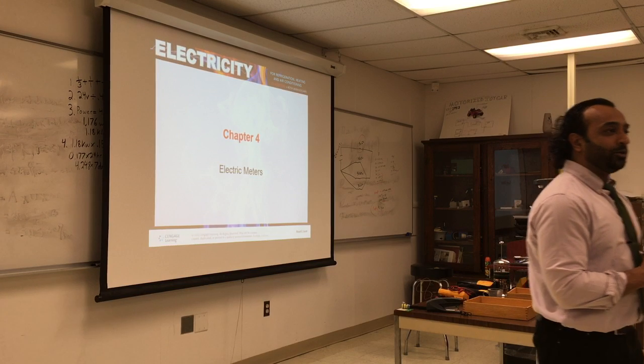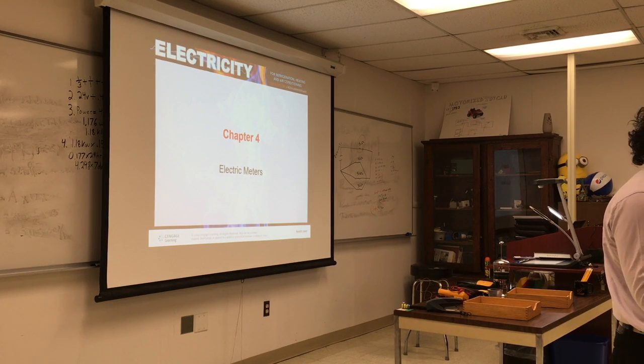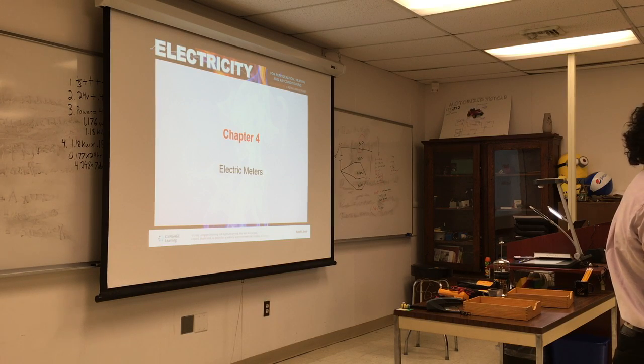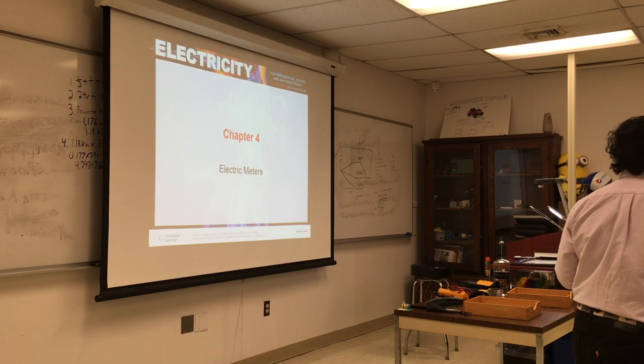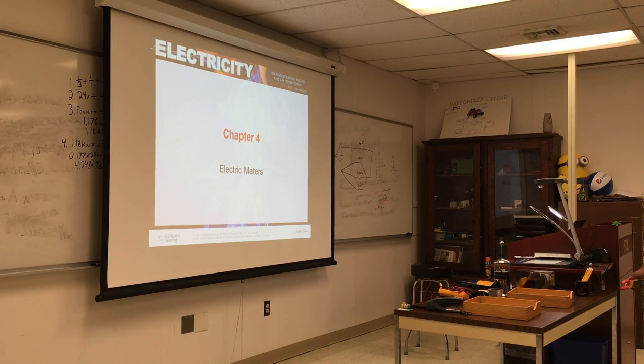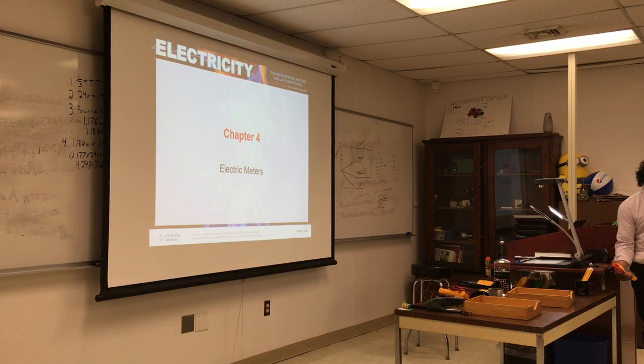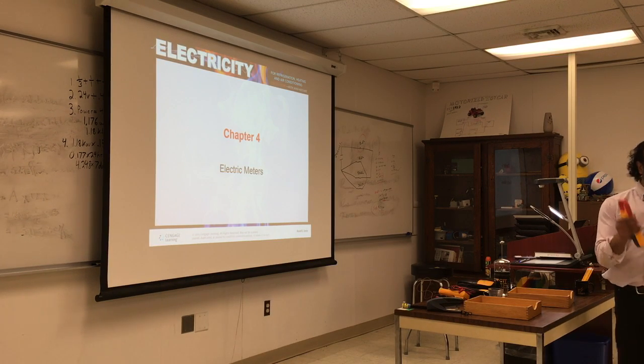When you measure amperage, you want to measure it when the equipment is live. You're going to clip this on the wire, not both wires. I'm going to ask you this at least 7 times: do not clip this on both wires, because the reading is going to be 0, because they're going to cancel each other. So you're going to take the wire apart and clip it on one.